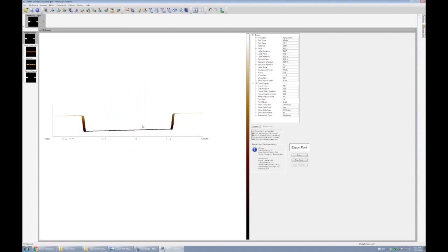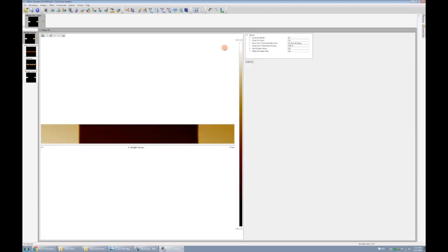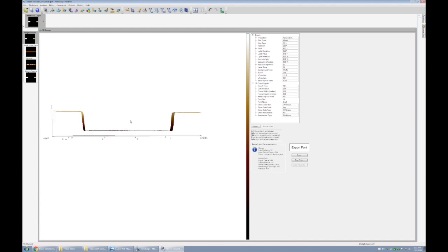So remember, we did a line plane fit in real time, but we offlined it without a plane fit. So I think I'm gonna go into plane fit, and typically I'll do an XY first order plane fit. And if I execute, you'll see that it kind of flattened everything out. And if I go back to the 3D model, it looks flat.